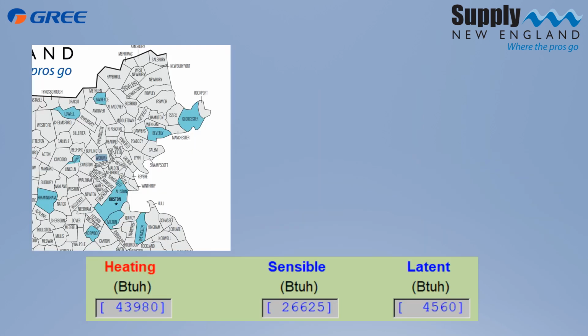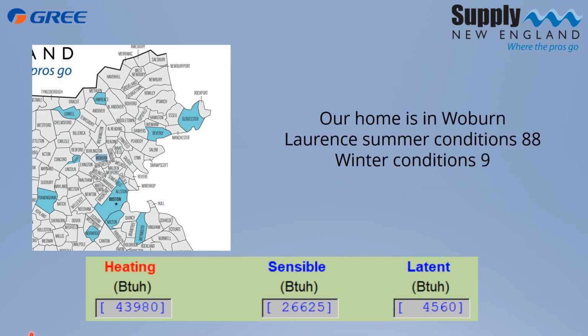Now let's look at our outdoor design conditions. Our home is here in Woburn. These dark blues that you're seeing here are what Wrightsoft has for design towns. So our closest town is Lawrence, Mass. In Lawrence, the high in the summer is 88, and the low in the winter is 9. So that's what we're going to be designing around. Based on that information, at 9 degrees outdoors and 70 degrees indoors, our heating BTU requirement is 43,980.